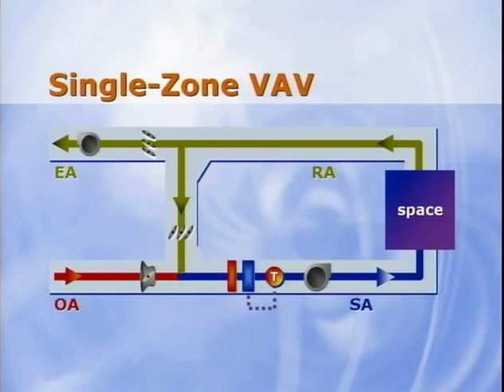In a traditional multiple-zone VAV system, a temperature sensor in each zone modulates a VAV box to vary the volume of supply air delivered to that zone. At the same time, the central supply fan modulates to maintain pressure in the supply ductwork. On the other hand, a single-zone VAV system serves only one zone. No VAV boxes are used. Instead, a temperature sensor in the zone is used to directly vary the airflow delivered by the supply fan. And like a conventional VAV system, cooling capacity is modulated to maintain a discharge air temperature set point.